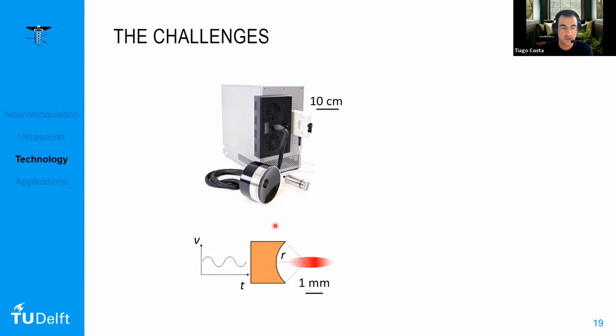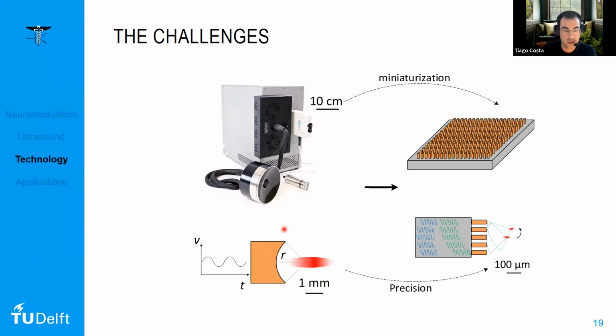Because with movement, even if we have a position correct at the beginning, with movement or the pulsation of the brain, the focal spot will no longer be in the right location. So the challenge is twofold. First, miniaturize these gigantic boxes into microchips, so that we can either make it a wearable patch or insert it into the body in a minimally invasive way, and try to increase the spatial resolution also from millimeter size to the hundreds of micrometers or below, to continuously push spatial resolution towards the size of single neurons. And the advantage that I didn't mention is the ability to change the focal spot location electrically or electronically without relying on movement. And this is achieved by beamforming, as I'm going to explain.